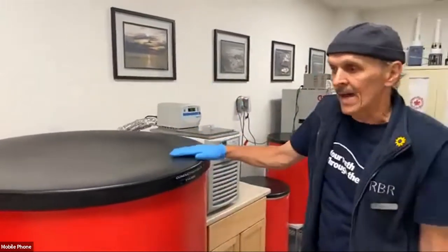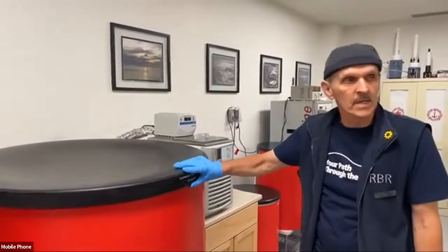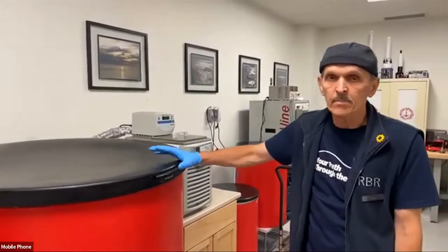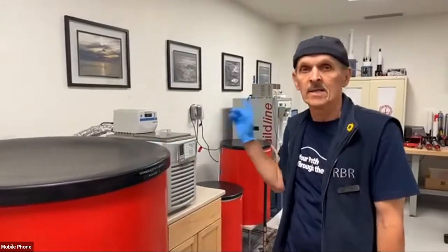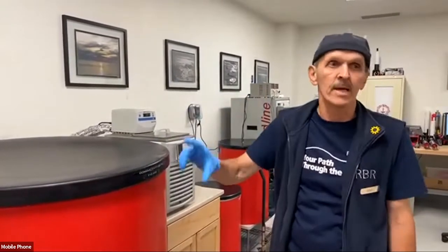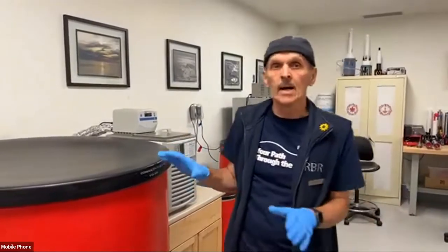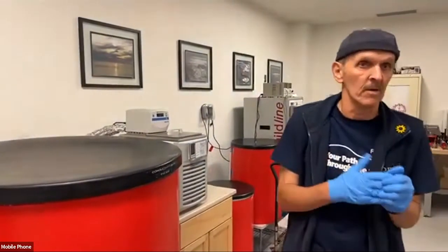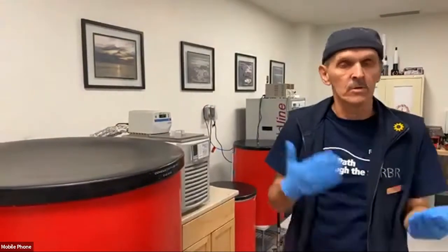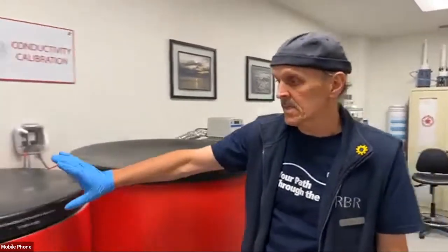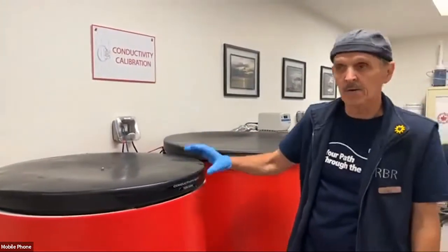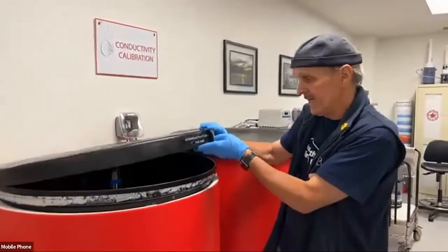That's the primary calibration point. We keep 15 degrees for one reason: the practical salinity scale was built at 15 degrees, and the standardization of standard seawater happened at 15 degrees too. So all standard conditions of measurement in conductivity conversion to salinity are based on 15 degrees, which is the mean temperature of the ocean, and it's well distributed in the temperature scale. The second bath is simpler. It's kept around 25 degrees and doesn't need any stabilization.